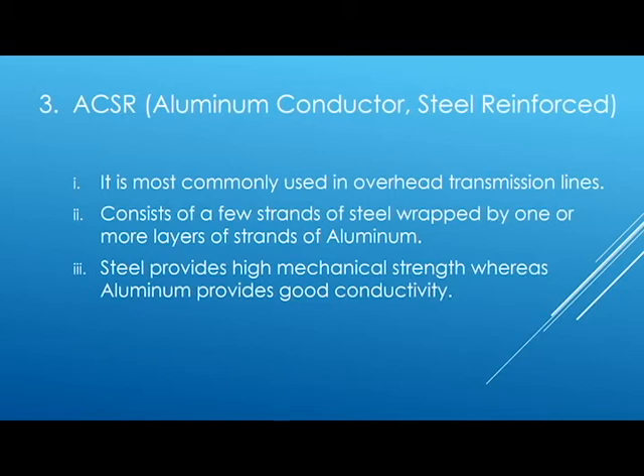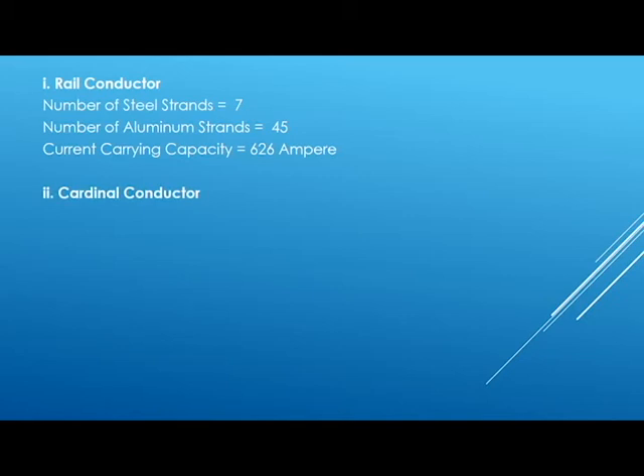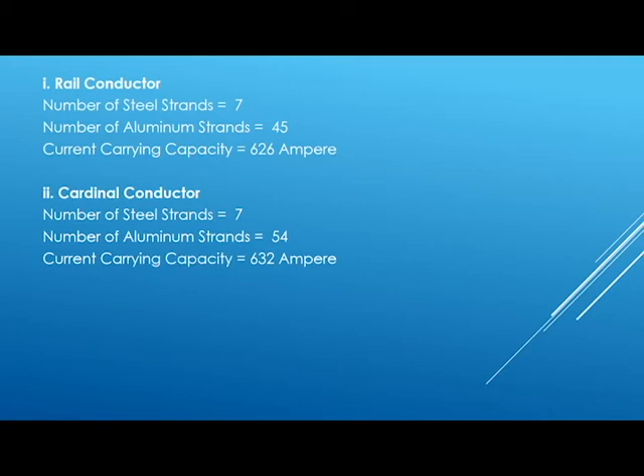Steel provides high mechanical strength, whereas aluminum provides good electrical conductivity. Examples of ACSR conductors are Rail, Cardinal, and Zebra. In the Rail conductor, the number of steel strands is 7 and aluminum strands is 45, with a current carrying capacity of 626 amperes. In the Cardinal conductor, the number of steel strands is 7 and aluminum strands is 54, with a current carrying capacity of 632 amperes.